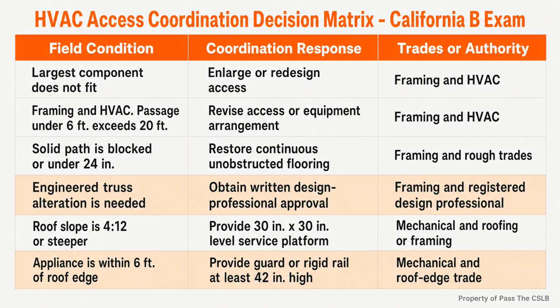Imagine a rooftop unit placed 4 feet from an open edge to preserve an architectural sightline. The unit needs routine service and the edge has no parapet or guard. The visual preference does not erase the clearance condition. The contractor has to coordinate the required protection before treating the equipment placement as complete.